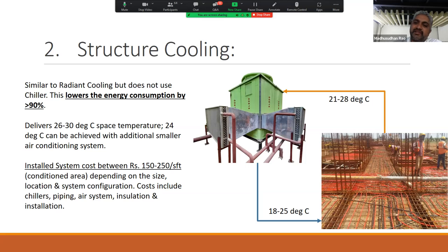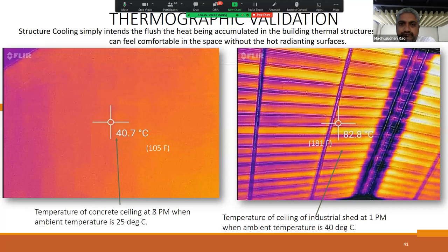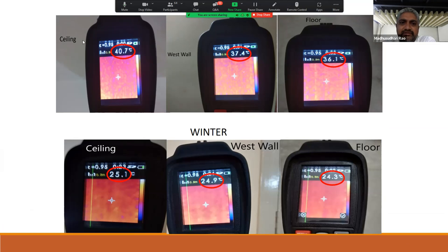So what we do is embed a network of pipes in the structure, just like radiant cooling. But instead of using a chiller, we use a low energy system like a multi-stage cooling tower. Here we have used a multi-stage cooling tower, or some other sort of heat sink that I'll talk about in the next section. So I'll just show a few thermographs. These are the temperatures taken of a space in summer. You will see the ceiling temperature.